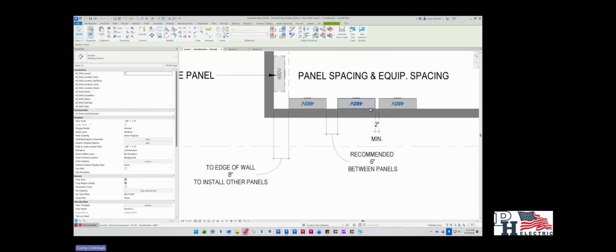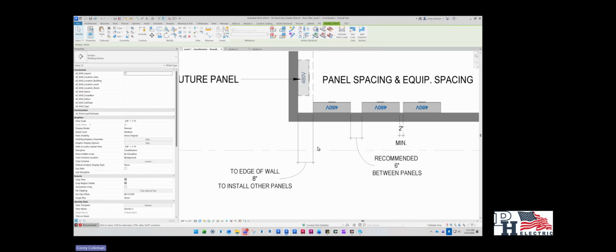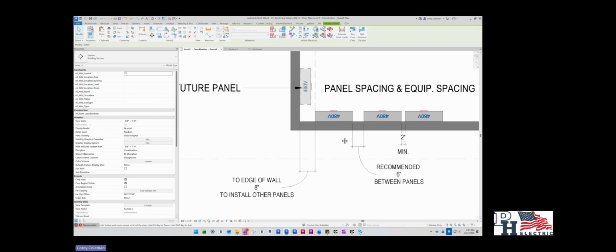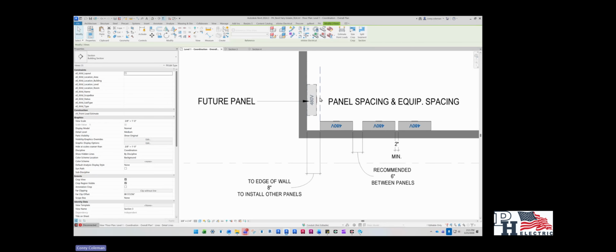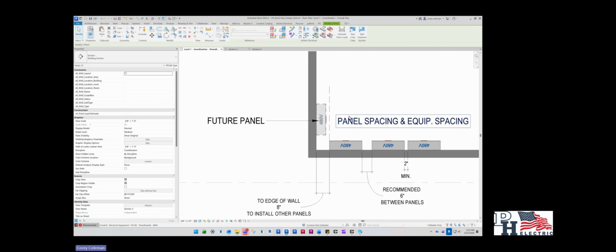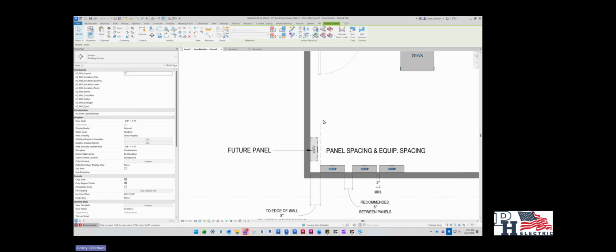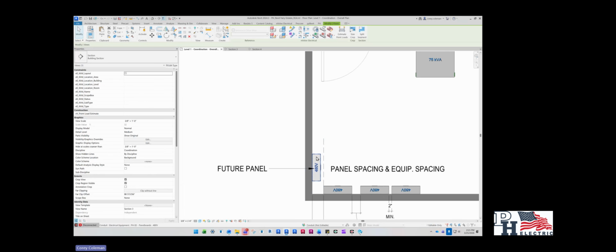If you do have to make panels tight, 2 inches minimum is what's recommended. That's what a lot of the foremen that we have in the field work with. So 2 inches should be your spacing. And then if you're going to be placing a panel next to a wall and you want to leave future space, you want to leave 8 inches of space between the wall and that panel that you're installing. That allows a future branch panel or smaller distribution panel to be installed in the future.